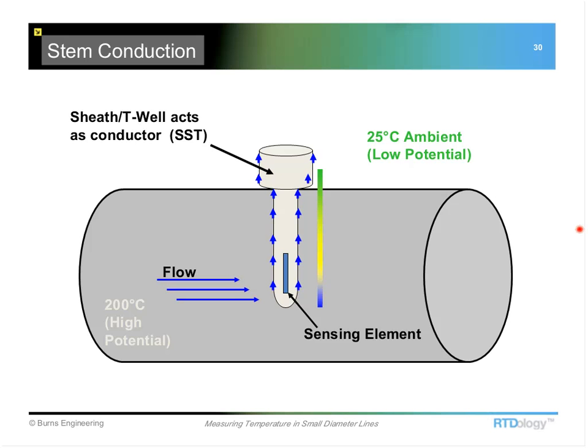So again, there are ways to overcome that, and Bill's already gone through some of those solutions, but I just can't stress enough the importance in the small diameter line that you can't just go smaller with it. You need to take into account many different factors in order to make sure you're getting the measurement that you want, not just a measurement, because any sensor will give you a measurement, but you want to make sure it's measuring what you've got going through that pipe, not just the pipe itself. Right. Yep, that's a good point.